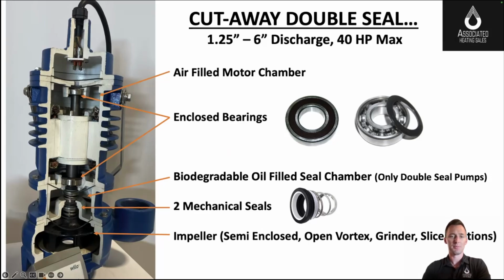But the big difference you might see between a Wilo pump and a more budget, off-the-shelf residential pump versus commercial would be these heavy duty castings with an air-filled motor chamber. You'll see the competitors in the space where it's commercial, even municipal, stick with air-filled motor chambers. The idea is that an air-filled motor chamber, if it's asked to run continuously, would cool down with the cooling fins a little more rapidly than a hot bath of oil. You see a lot of pumps with oil-filled motor chambers that are at just a different price point and a different application. So Wilo stuck with this design.